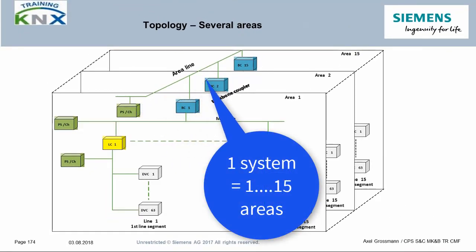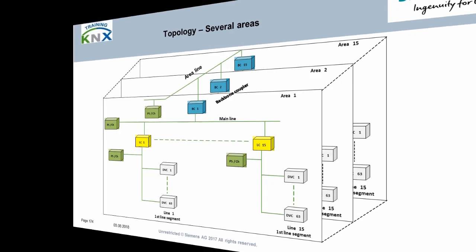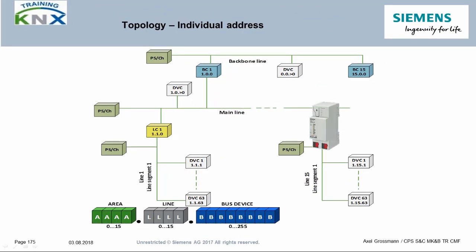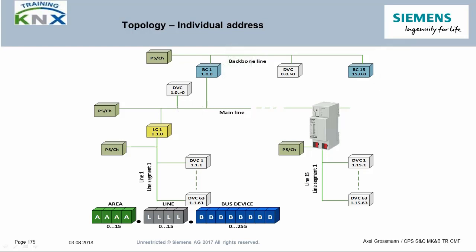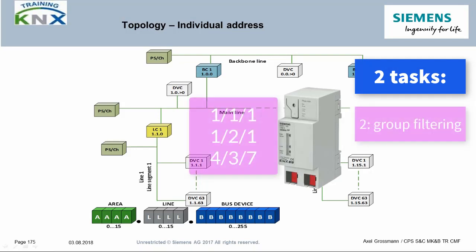A total of 15 areas can be created. Exactly the same conditions apply to each area as previously explained. Area couplers are used to connect the areas with each other — they connect logically and isolate electrically. As already heard in the topology chapter, all couplers are identical in terms of hardware; the distinction is made via the physical address. Couplers have two different filter tasks: they filter bus telegrams whose target address is physical by comparing them with their own physical address, and they filter bus telegrams whose target address is a group address by comparing them with a filter table stored in them.